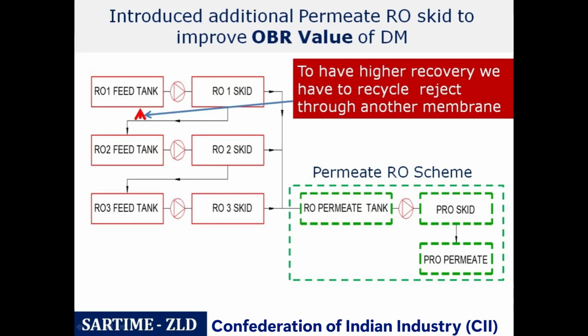The third improvement we make in the RO plant is to take the permeate from the RO plant. Typically, permeate from an RO plant will have 100 TDS. You again feed it through the RO plant again. That way the permeate TDS will become 30. With 30 TDS, our MB DM plant will achieve an OBR of more than 15 days. This way you can save a lot of chemicals in regeneration, because if you use a DM plant, for every 1 kg of salt removed, you are generating 2 kg of waste. So we are intensifying the use of the RO plant because we are only physically separating it. That way we are reducing the waste that is coming.